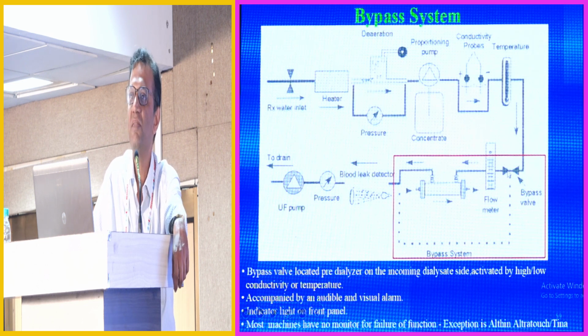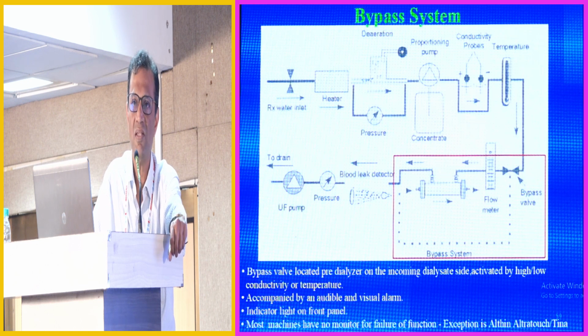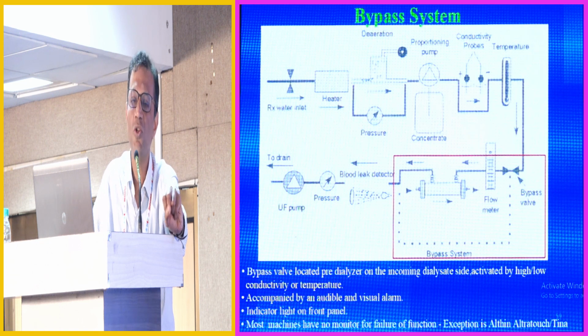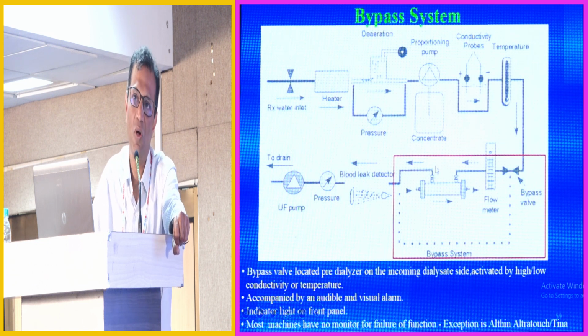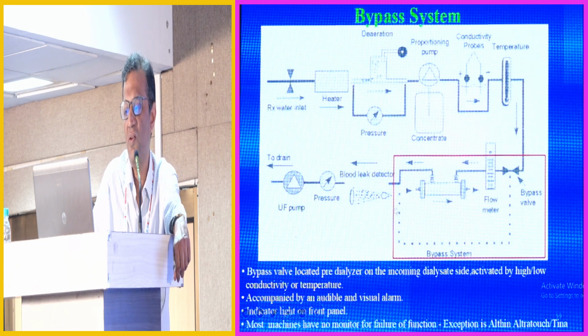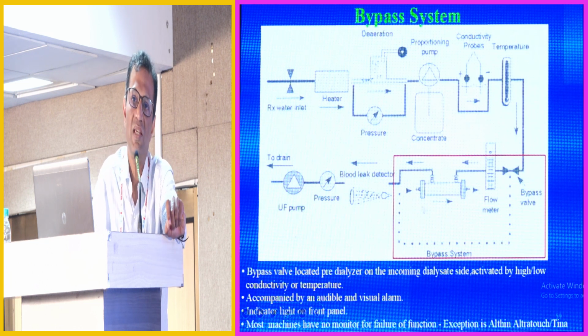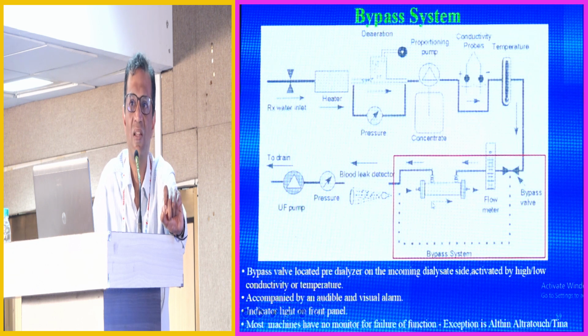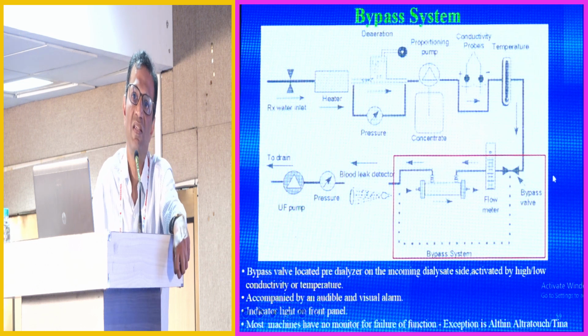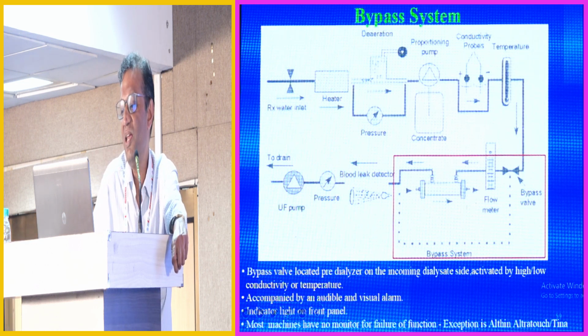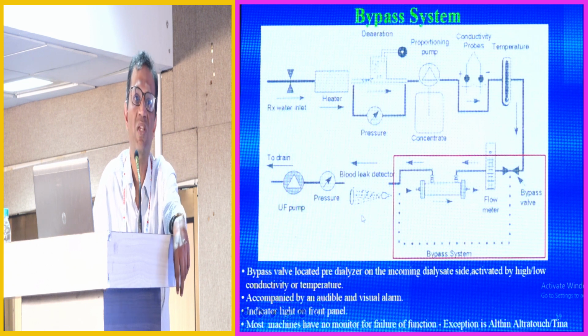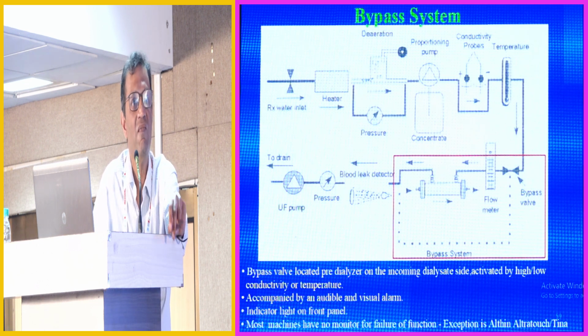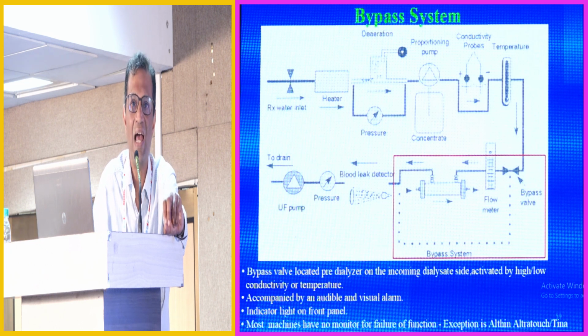And normally, this bypass valve will open and bypass it, and the machine will display on the screen that the machine is in bypass. It will also be accompanied by an audible and a visual alarm, and it can also be done manually when we want to. However, in most cases, we have to take the machine's word that the dialysate has been bypassed. If the bypass valve is dysfunctional, the display will still say machine in bypass. The exception again is Althin Altratouch, which has 2 flow sensors on the bypass path. If the machine, when in bypass, does not detect dialysate in the bypass line, it will shut down automatically.